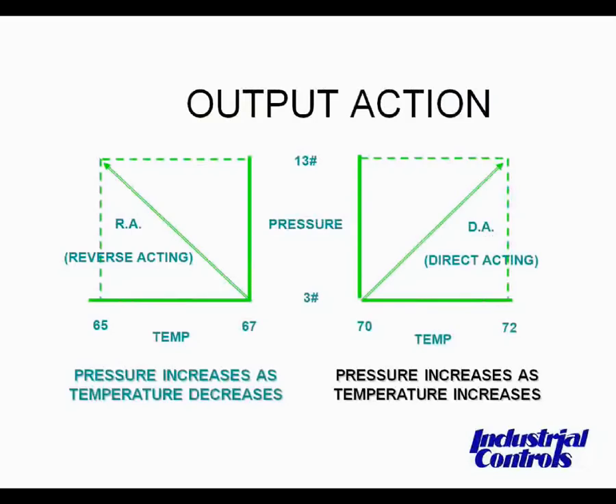In proportional control, things aren't quite so simple. We need to look not only at the action we want, but also what the safe position of the valve or damper should be. Pneumatic actuators all have springs under their diaphragm. This means that the actuator will always go to a normal position on loss of air pressure. It's up to the person who engineered the job to make sure the actuators take the proper normal position and also work properly.